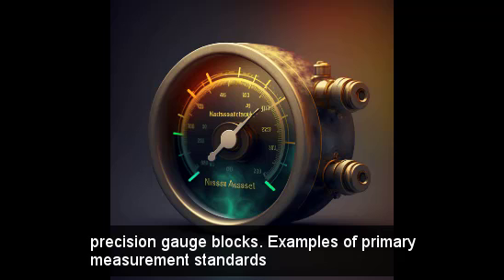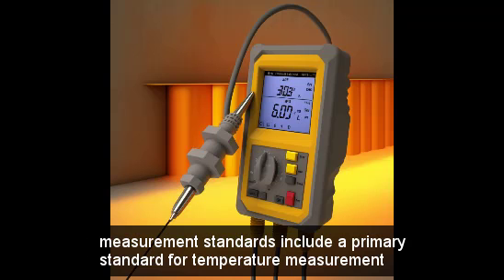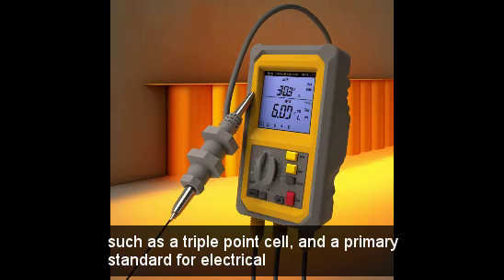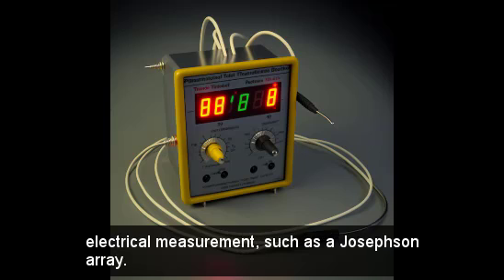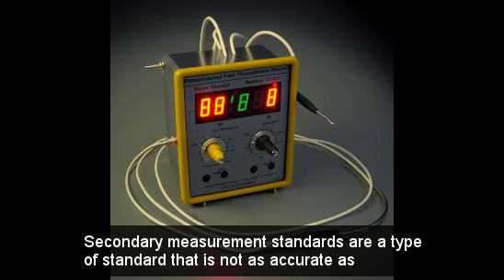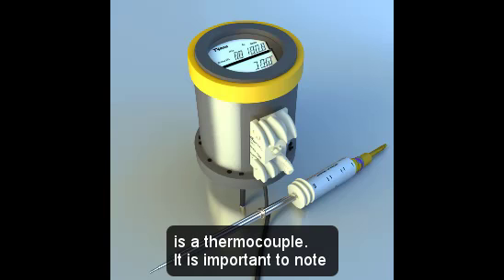Examples of primary measurement standards include a primary standard for temperature measurement, such as a triple-point cell, and a primary standard for electrical measurements, such as a Josephson array. Secondary measurement standards are a type of standard that is not as accurate as primary measurement standards but can still be used to calibrate equipment. These standards are typically calibrated using primary measurement standards. An example of a secondary measurement standard is a thermocouple.